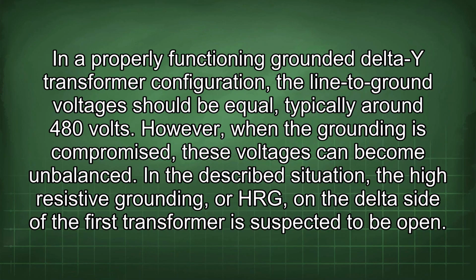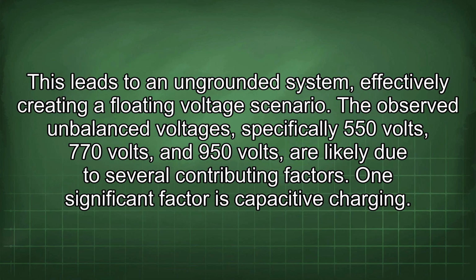In a properly functioning grounded delta-Y transformer configuration, the line to ground voltages should be equal, typically around 480 volts. However, when the grounding is compromised, these voltages can become unbalanced. In the described situation, the high resistive grounding, or HRG, on the delta side of the first transformer is suspected to be open. This leads to an ungrounded system, effectively creating a floating voltage scenario.